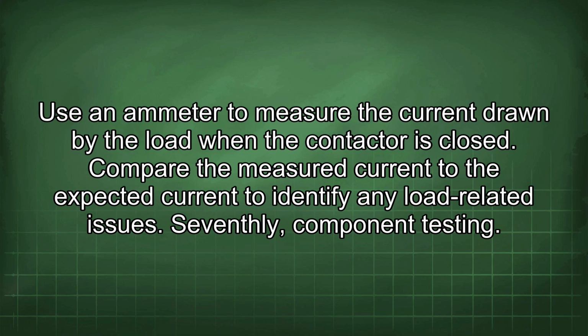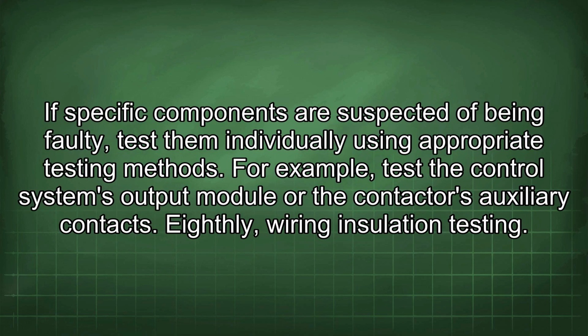Compare the measured current to the expected current to identify any load-related issues. Seventhly, component testing. If specific components are suspected of being faulty, test them individually using appropriate testing methods. For example, test the control system's output module or the contactor's auxiliary contact.